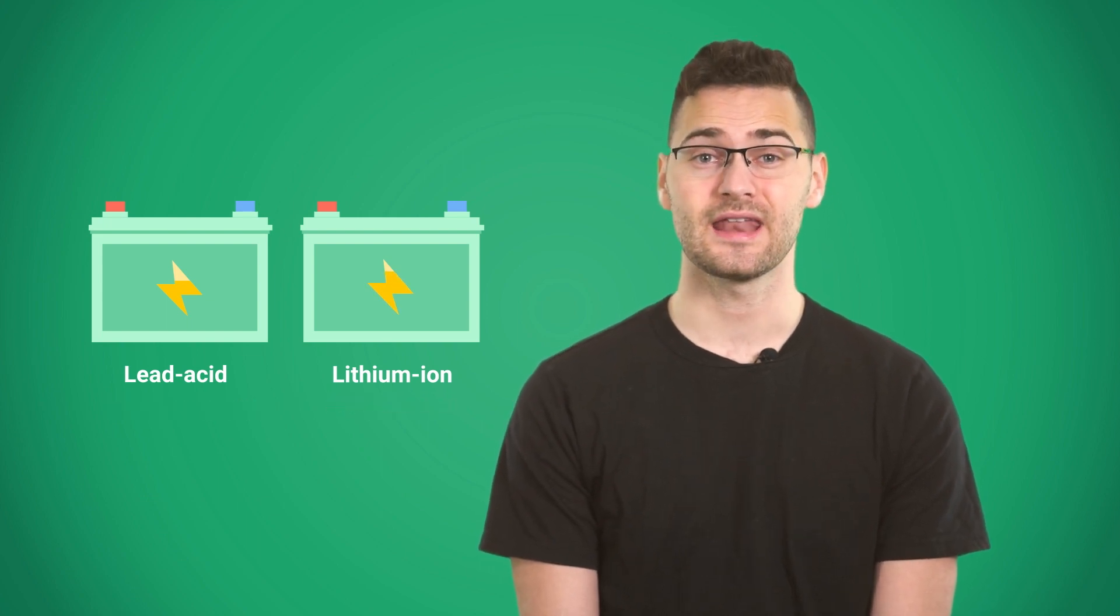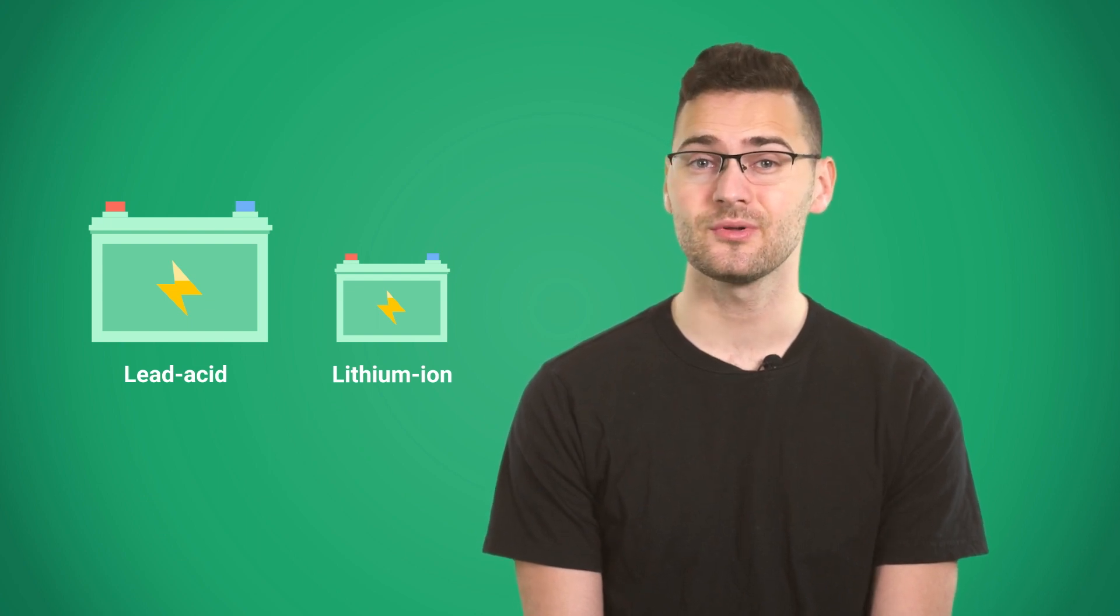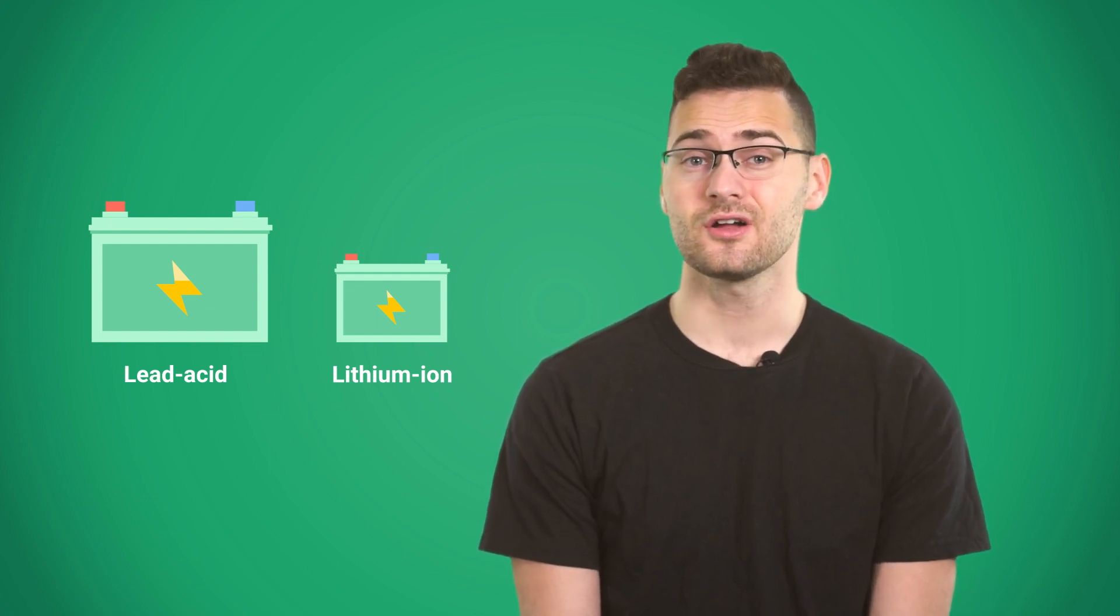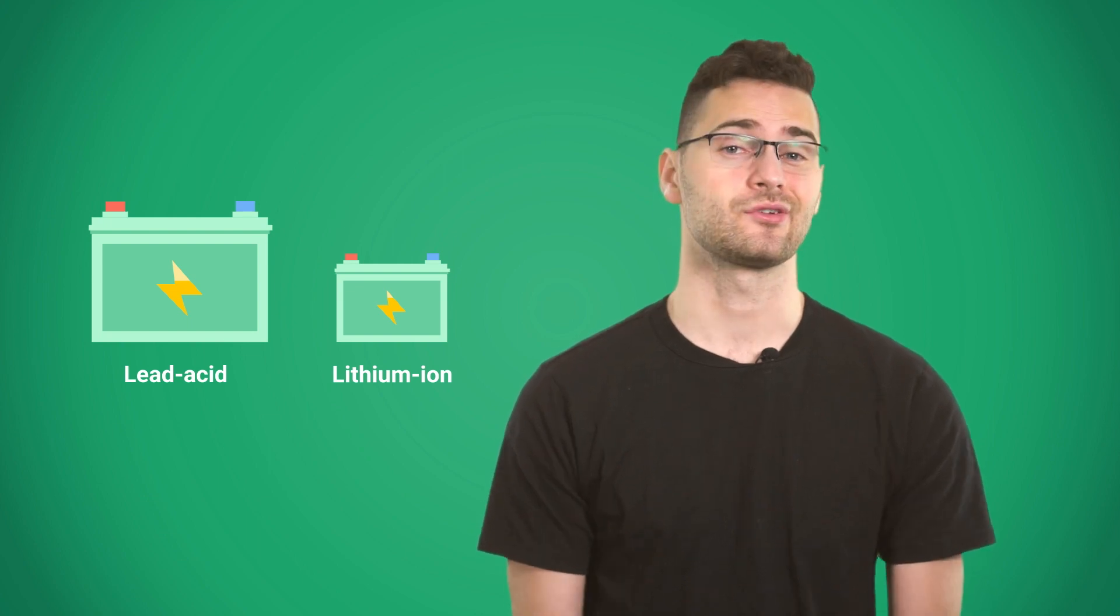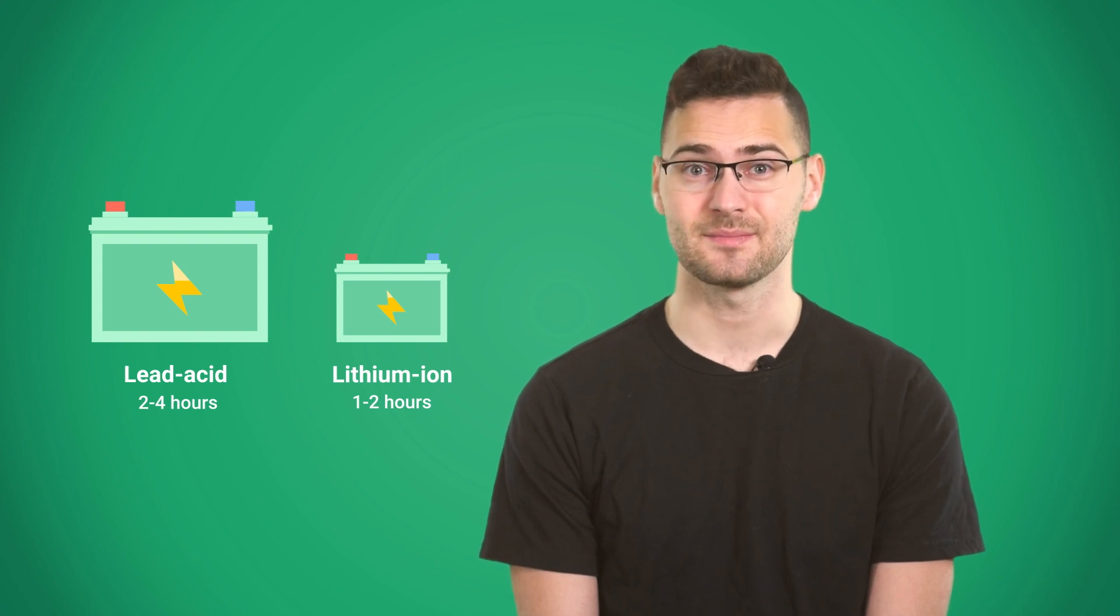A lithium ion battery, on average, occupies 75 percent less space and weighs 75 percent less than a comparable lead acid battery. They are also charged faster. It takes about one to two hours to fully charge a lithium ion battery compared to two to four hours for a lead acid battery.